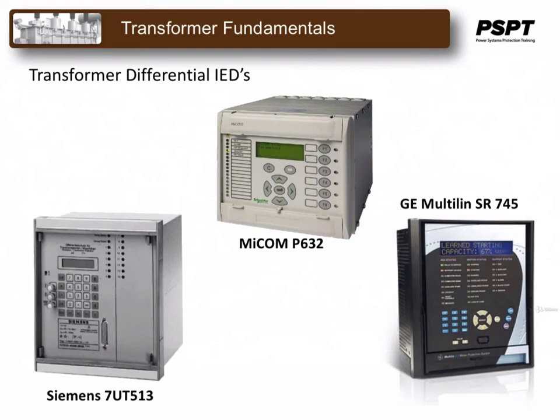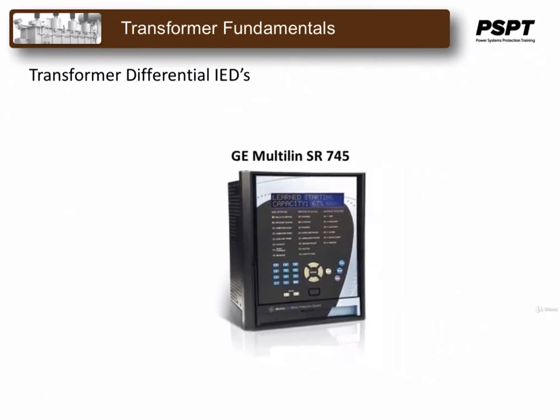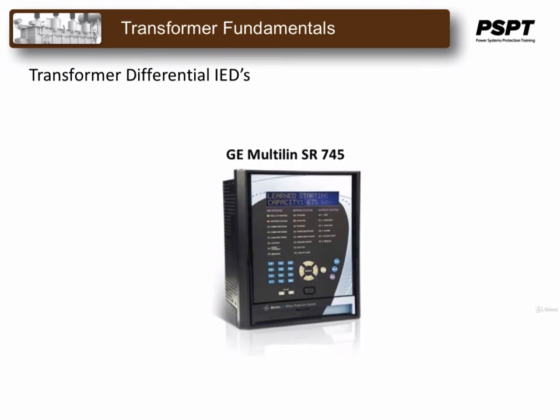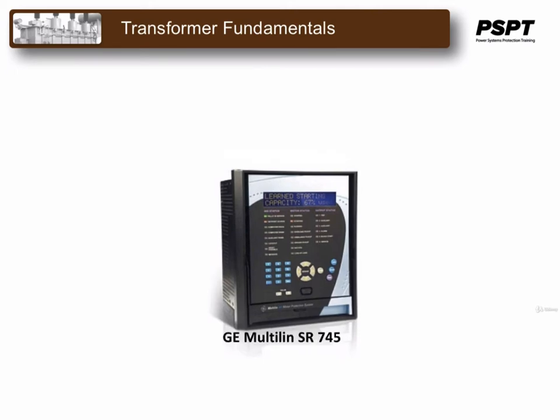them to another relay. Let's take a closer look at one of these relays, and we're going to start out with the GE Multilin SR745. The 745 transformer protection system is a full-featured transformer protection relay suitable for applications on small, medium, and large power transformers. The 745 can be applied to 2-winding and 3-winding transformers.